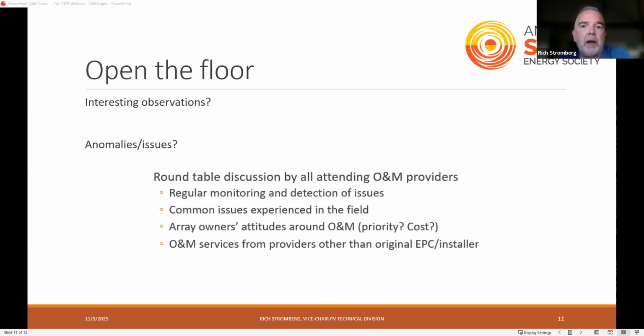I was able to look at the string inverter data, just voltage across all the strings at the site, and I noticed one anomaly out of 4,000 modules. I walked the string of 18 modules and found a junction box with a thermal issue. And that was before I even hit the site.